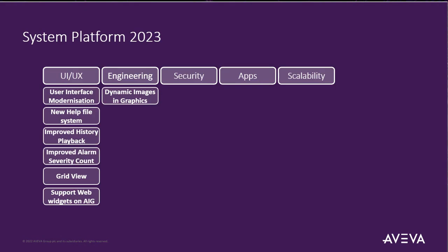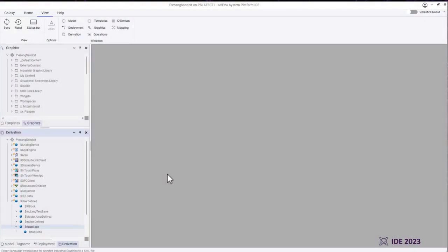Next up is the big string data type. This is quite an interesting one. We've got the string type in, we always had the string type in Application Server. It has some limitations, 1024 characters to be exact is that limitation. And that works for general strings. You wouldn't even have noticed it, but in more modern applications, we see a lot of people working with XML and JSON and CSVs and large string types. So what we've done here is we've added the ability to expose a big string. Now, big string actually did exist in the past. We just made it visible now so users can directly access it.